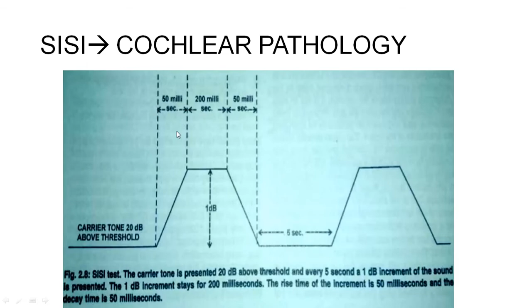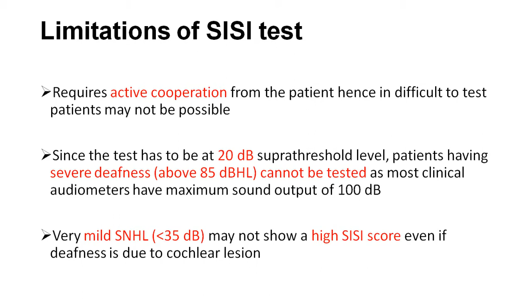The limitations of the test are that it requires active cooperation and has to be done at 20 decibels above threshold, so severe deafness cannot be tested. Whenever there is severe deafness, above 85 decibel hearing loss, you have to go for something called ASSR, auditory steady state response. Very severe deafness can be tested by auditory steady state response. It's not USSR, it is ASSR. In case of failure of any other test, with more than 85 decibel hearing loss, you have to go for ASSR, which we are not going to deal with today. Mild sensorineural hearing loss may not show a high score even if deafness is present. There are limitations for every test which you need not remember in detail, but you should have a basic idea.